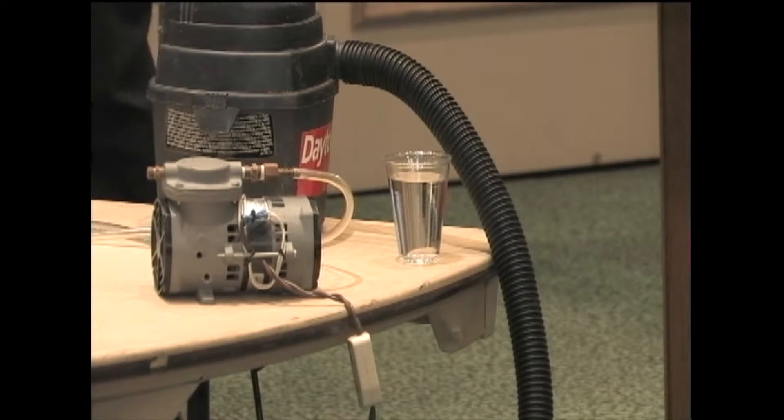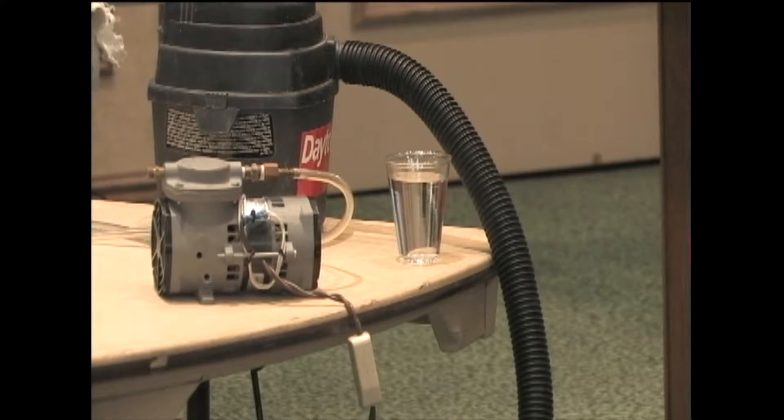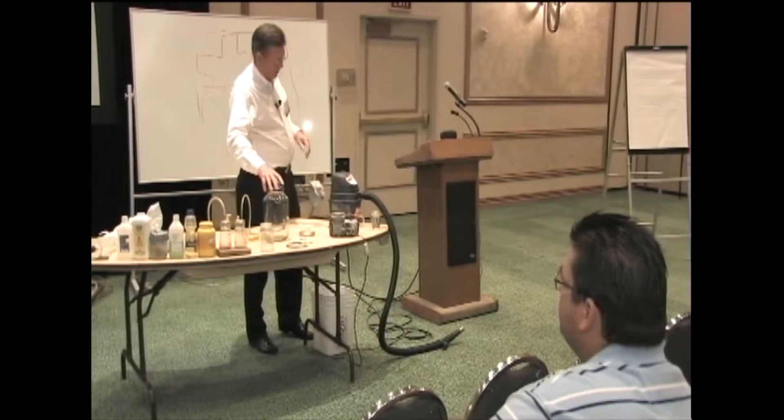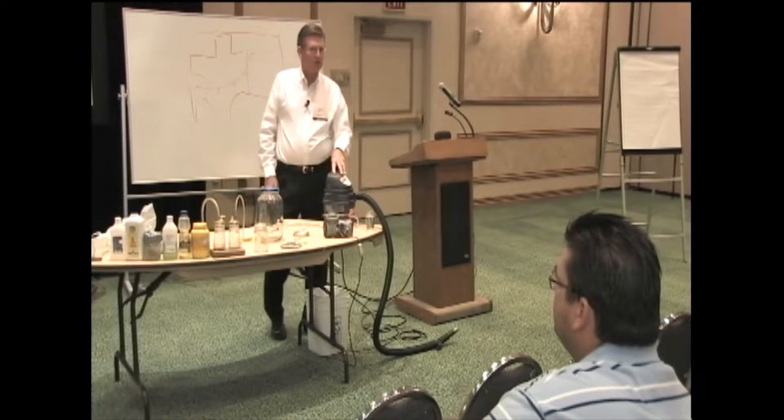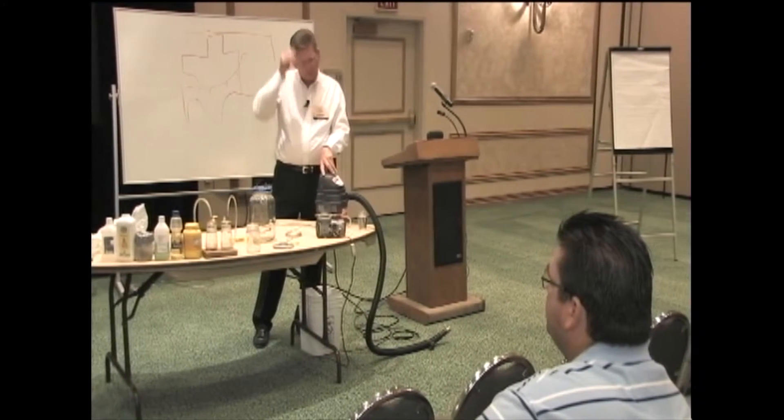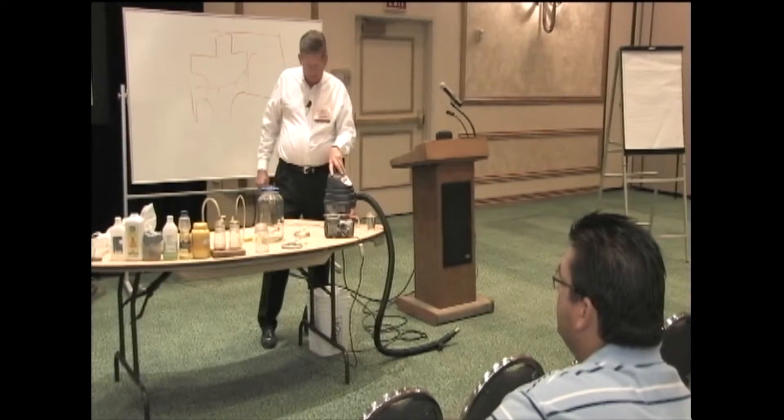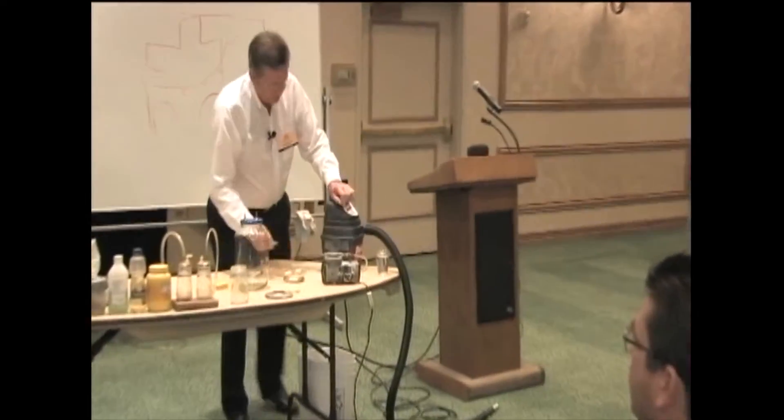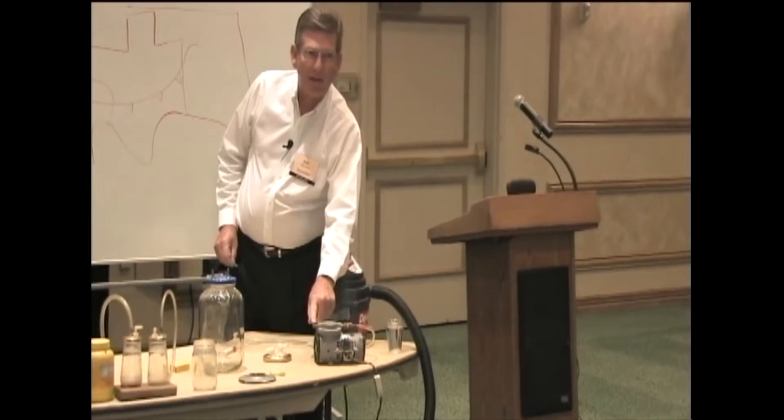It only moves three quarters of a cubic foot per minute. About this much air is all it moves per minute. It's going to vacuum. It will produce 22 inches of mercury, we'll get into what that means in a few minutes. But what I want to do is first take the pressure side, which is this side of the vacuum pump.